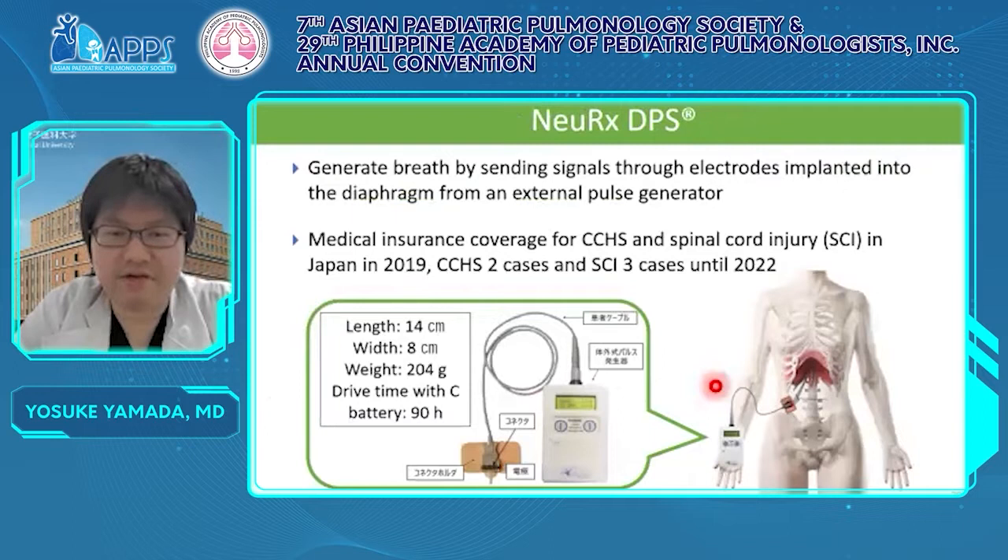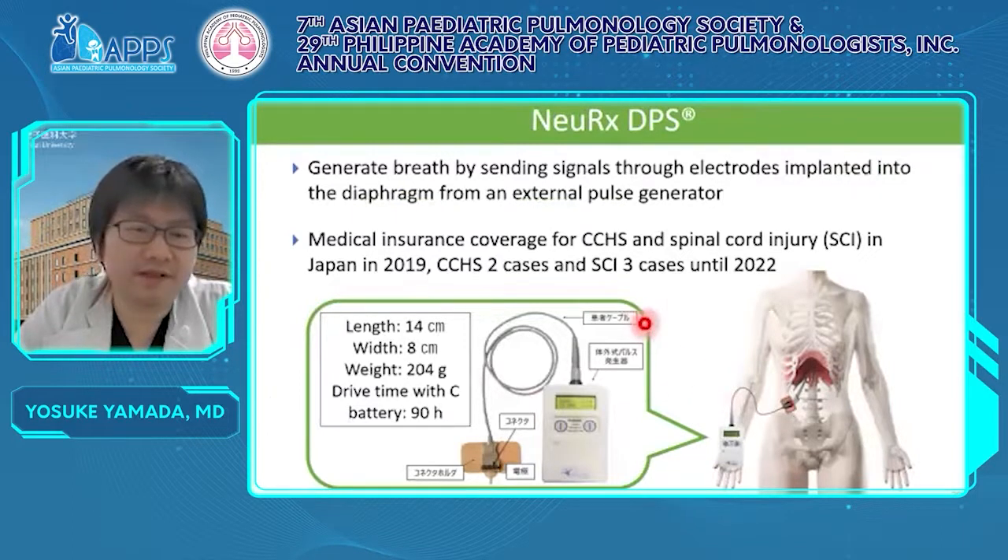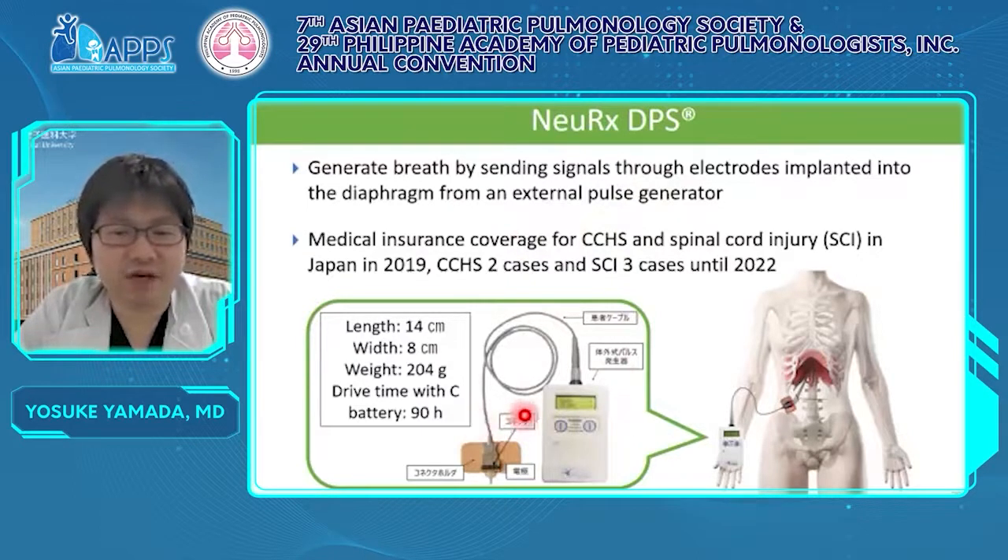This is the third respiratory management — diaphragm pacing (DP). We use the NeuRx DPS diaphragm pacing system in Japan. DP generates breathing by sending signals through electrodes implanted into the diaphragm from an external pulse generator. The pulse generator is small — palm-sized — weighing 204 grams without the battery. A C battery can drive DP for about 90 hours. Medical insurance coverage for CCHS and SCI started in Japan, and DP was implanted in two CCHS cases and three SCI cases until 2022.